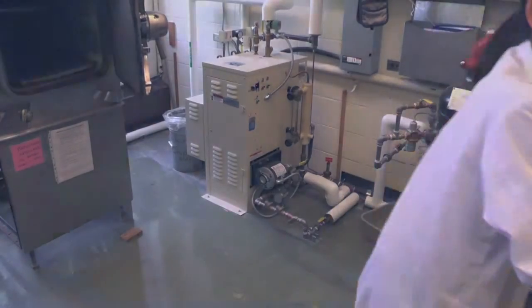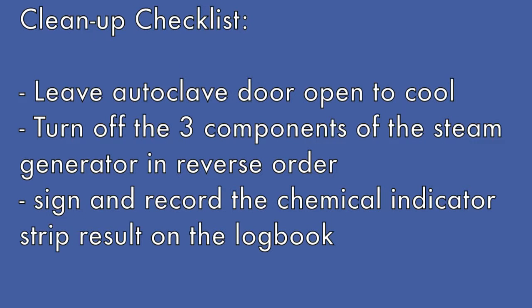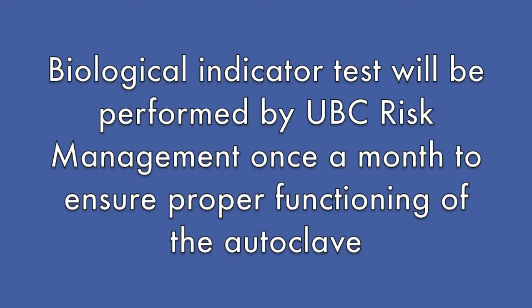Turn off the three components of the steam generator in reverse order. Ensure you have signed the logbook and record the chemical indicator strip result. Once a month, the technician will perform a biological indicator test as required by UBC risk management to ensure that the autoclave functions properly.